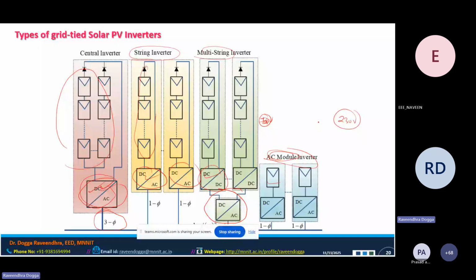If you're having a voltage source inverter, it will only step down, not step up. So if you have 400 volts DC input and need output for a load like this, you'd need 8 times gain from the DC-DC converter. That's not possible with classical converters like boost converters. Theoretically they can provide infinite gain, but practically they max out around 4 to 4.5 times. If you go above that, efficiency drastically decreases, so typically we limit to 3 to 4.5 times gain.